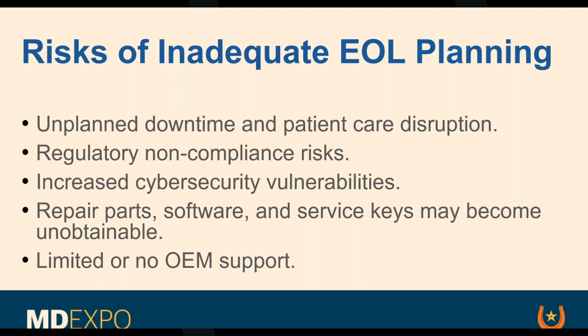The OEM must provide you whatever documentation, tools, service software, and service keys you need in order to do those four things: assemble the device, install the device, adjust the device, and then test the device. So if an X-ray tube fails and the OEM says, well, that system's end of life, we won't sell you the tube, we won't tell you how to fix it, we won't send somebody out there, two of those three things are okay, one of those is not. They do have to provide you the documentation and whatever service tools and software you need in order to perform the tube replacement. Now you have to be a qualified person, right? The FedEx guy who brings the tube can't just follow the documentation and install it. You have to have a reasonable background in HTM and the skill set to do it.